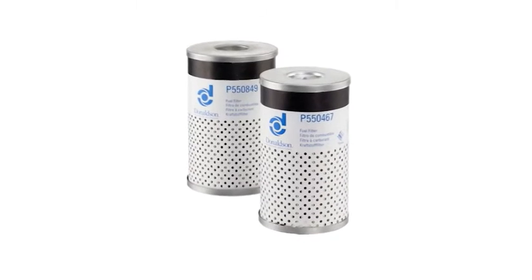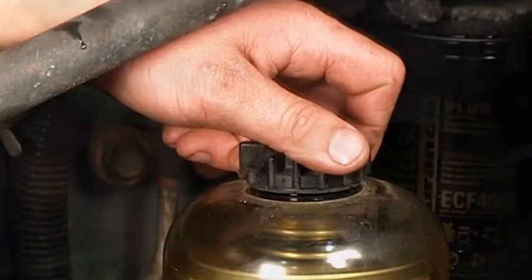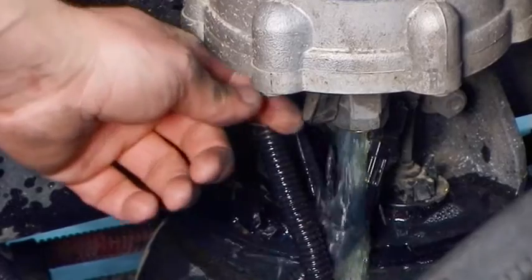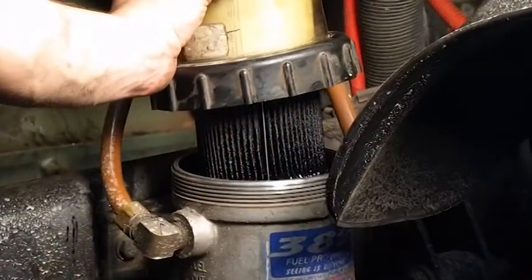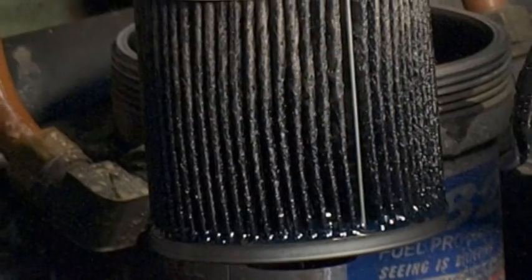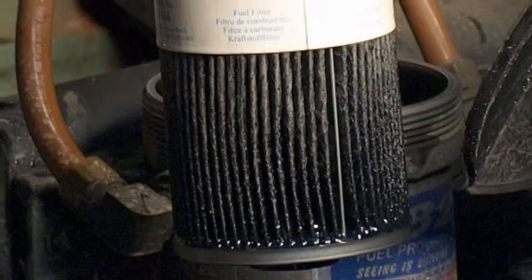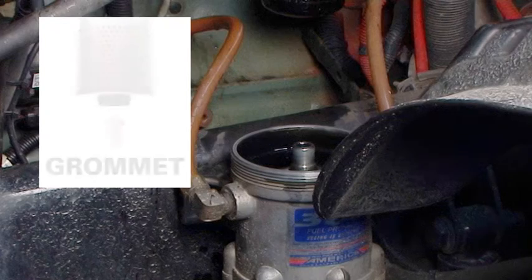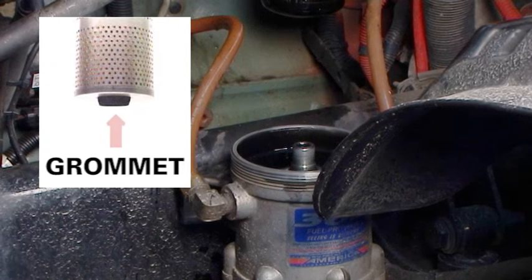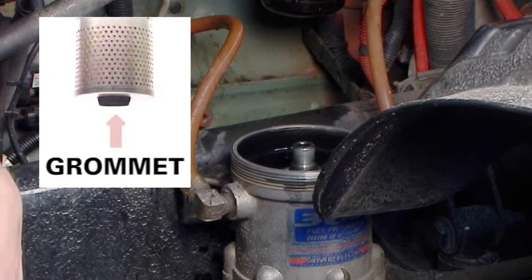For Davco-type cartridge filters, follow these steps. Remove the vent cap and open the drain valve to drain the fuel below the collar level. Remove the cover and collar. Remove the filter cartridge, cover seal, and vent cap seal, and dispose of them properly. If the grommet from the base of the cartridge has detached itself and remains behind on the stud, remove and dispose of it.